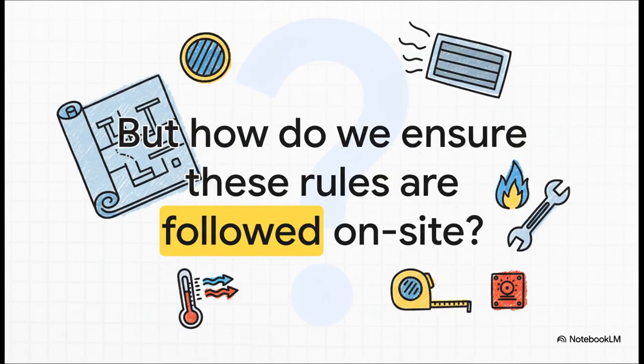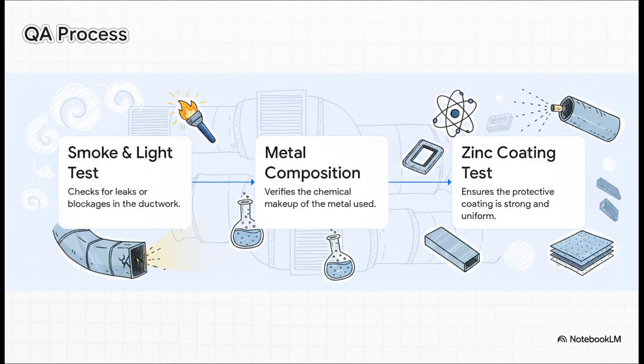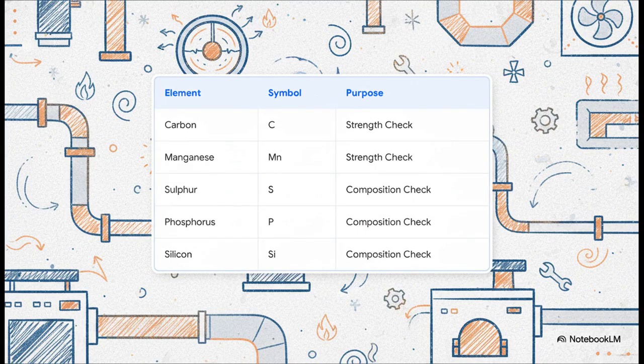Right, that's the big question, isn't it? It's one thing to have a rule book, but how do you know the system that's actually being installed, hidden away in the guts of the building, is following those rules? The answer? You test everything, rigorously. They actually run smoke and light through the ductwork to spot any tiny leaks that would waste energy. They'll test the chemical makeup of the sheet metal itself and even check the thickness of the protective zinc coating to make sure it won't rust away. And I mean, just look at this level of detail. They aren't just giving it a quick glance. They are doing a full-on chemical analysis, checking for specific elements like carbon and manganese for strength, and others to ensure the quality of the material. This is some serious industrial-grade science.